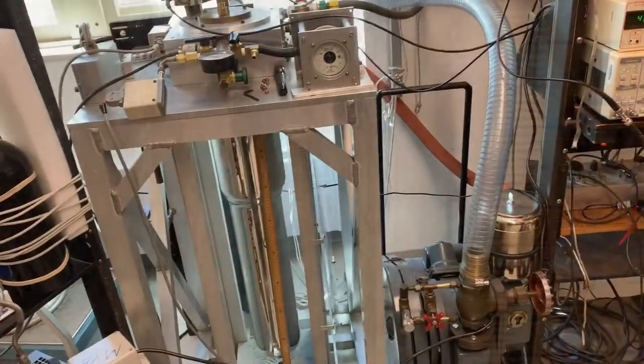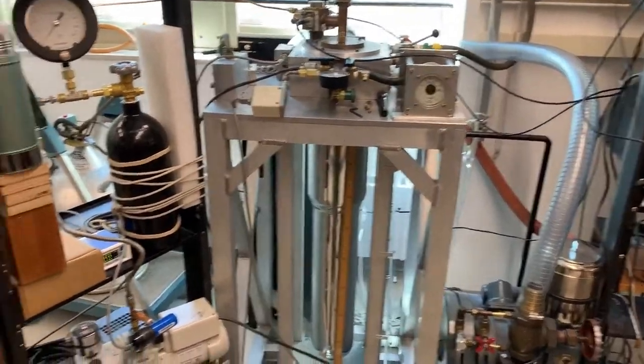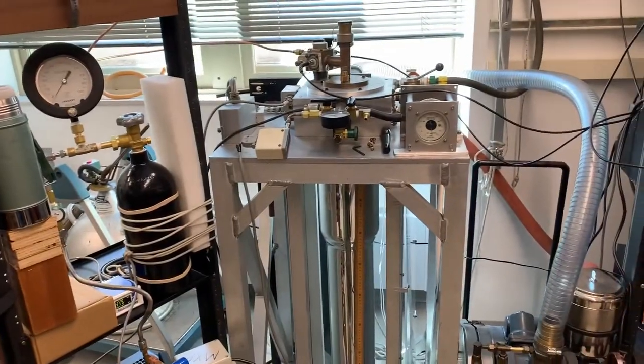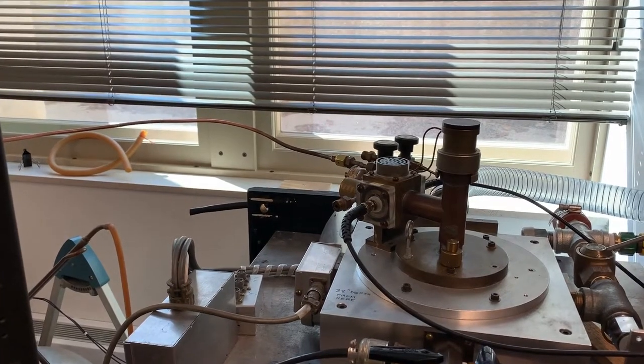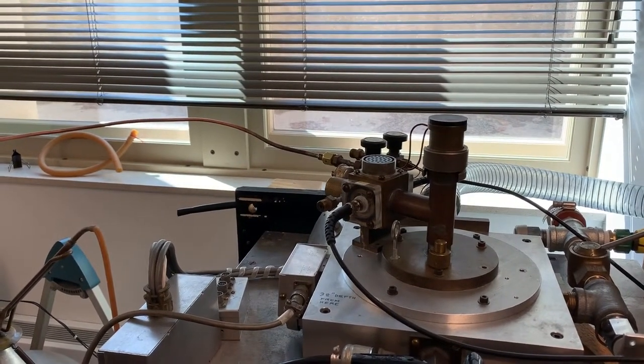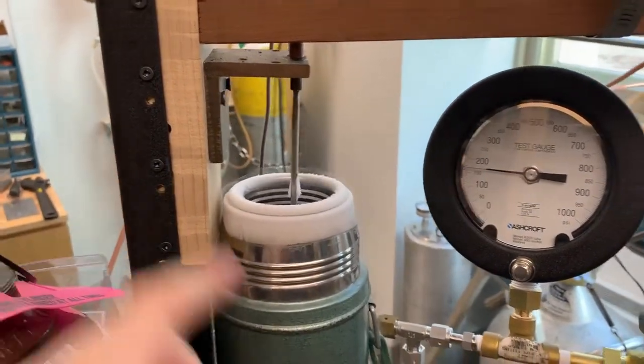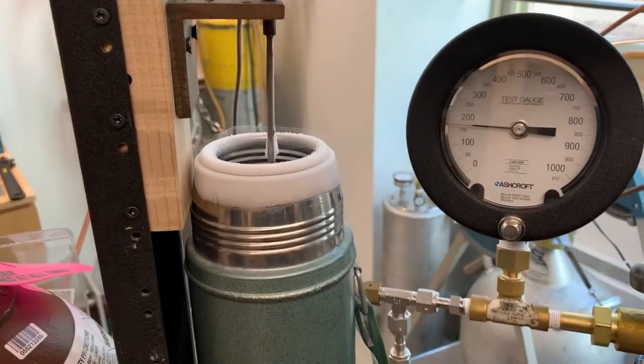Okay so we have begun pumping down the helium bath to get it to a sufficiently low temperature to start condensing helium once it's down a little ways I'll start feeding helium into the system. I've started to pressurize the part of the system that does not include the cryostat. That stop valve to the cryostat is still closed. We'll wait until it's sufficiently cool to actually introduce helium there. As soon as I turned on helium gas it flowed through the cold trap and it started boiling more vigorously so it is actually working the way it's supposed to which is very cool. That's the bubbling surface of the helium there you're seeing in front of the copper cryostat stem. It's bubbling so much because the vacuum pump is pumping on it trying to get it down to the lambda point. In order to make it a superfluid you have to boil off so much of it to get it there.